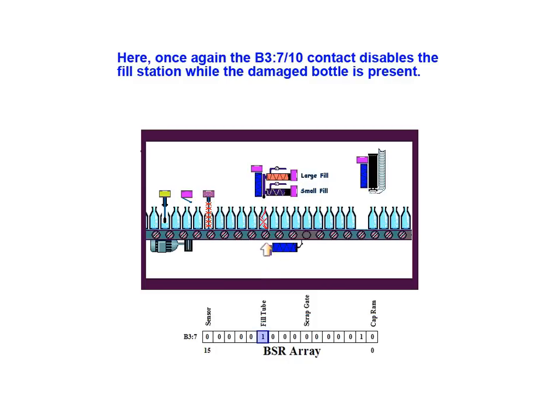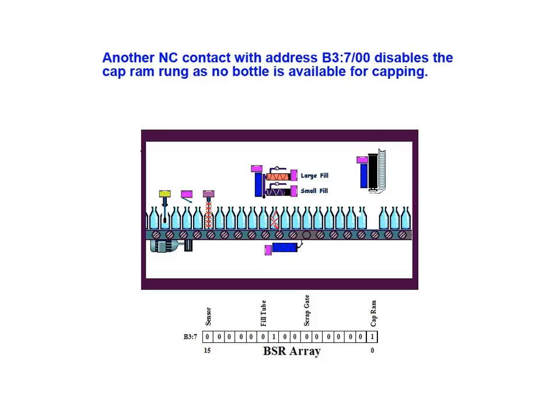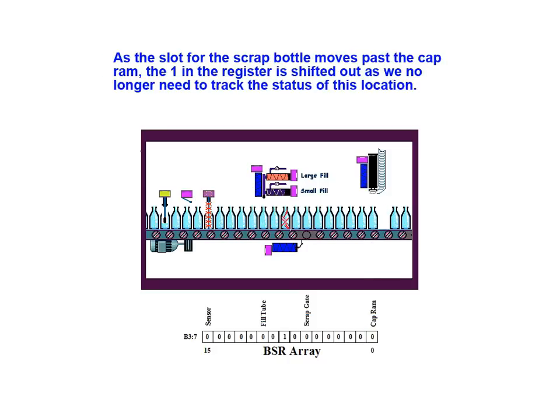The B37-bit 10 contact disables the fill station while the damaged bottle is present. Another normally closed contact with address B3:7/00 disables the cap ram rung as no bottle is available for capping. This was the empty slot left behind as the first damaged bottle was dumped down the scrap gate. As the slot for the scrap bottle moves past the cap ram, the 1 in the register is shifted out as we no longer need to track the status of this location.